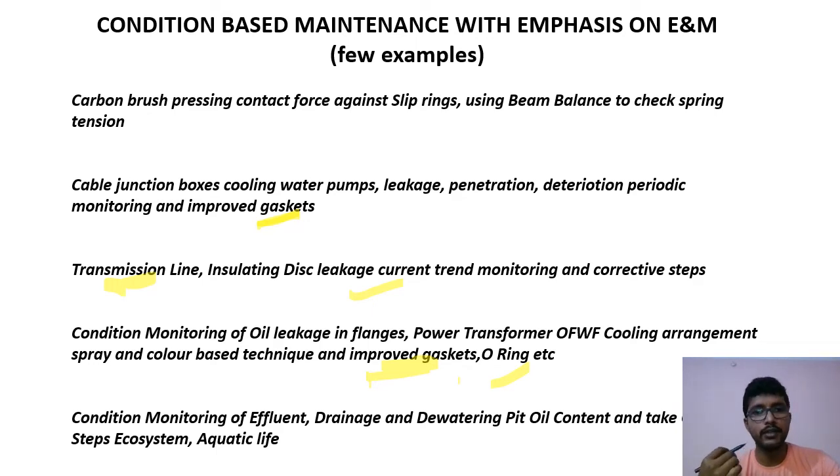We also need to check the trend. We need to see whether the condition is deteriorating or not with time. So it's a very effective way of understanding the behavior of the internal part of the transformer.